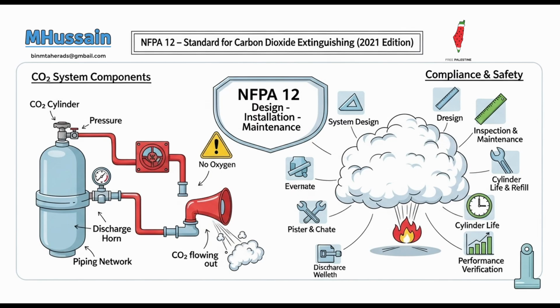For hazard specifications, the standard mandates that the entire hazard must be protected. This isn't just the visible fire, but includes all areas that could become coated by combustible liquids or shallow solid coatings. Cover everything that could burn. That means encompassing areas subject to spillage, leakage, dripping, splashing, or even condensation. This also extends to associated equipment like drain boards, hoods, and ducts that could potentially extend the fire. Think about where it could spread.